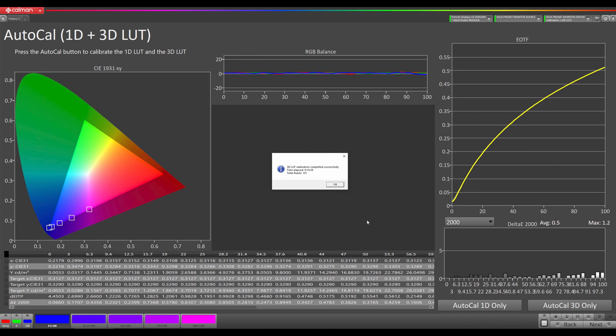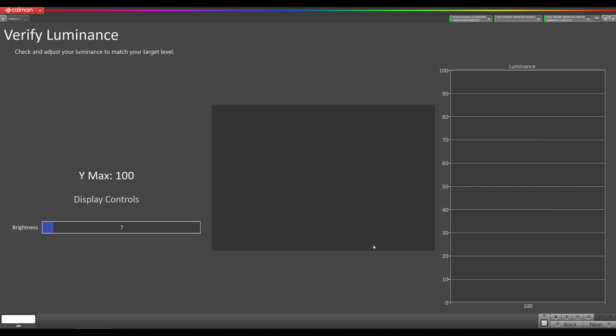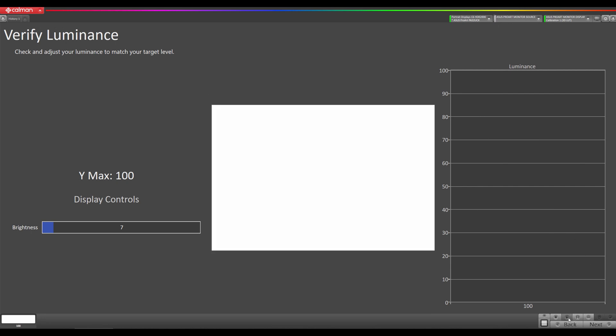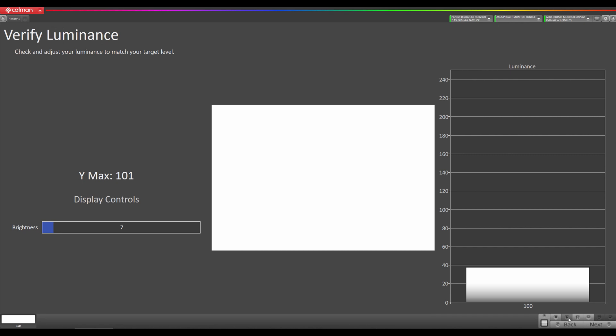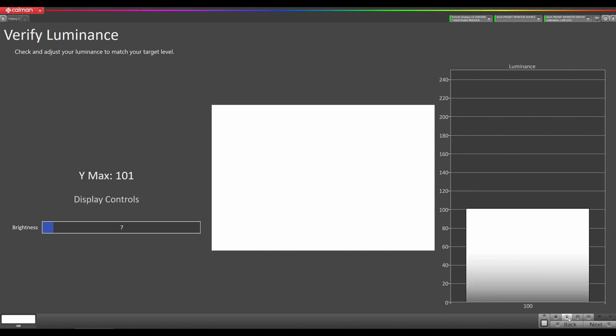Okay, our Lightning LUT took approximately a little over 10 minutes. So we're going to hit okay, then we're going to go to next and perform our verify luminance step. I'm just going to hit read single here, and we are at 101 nits, so we're good.